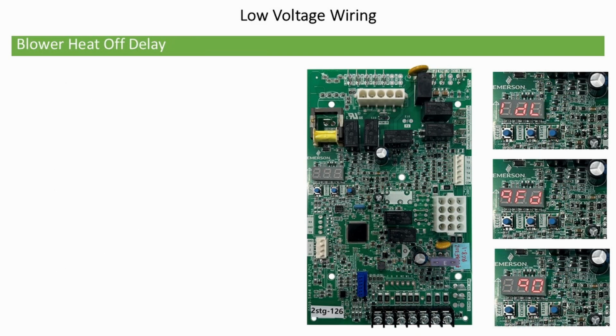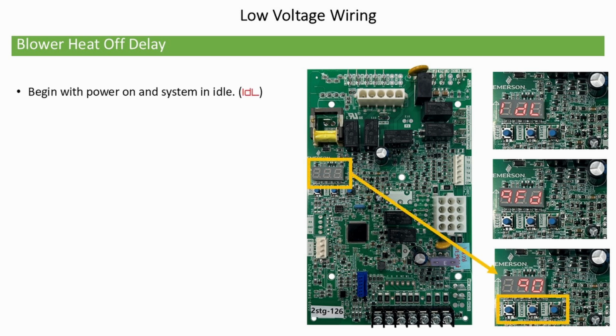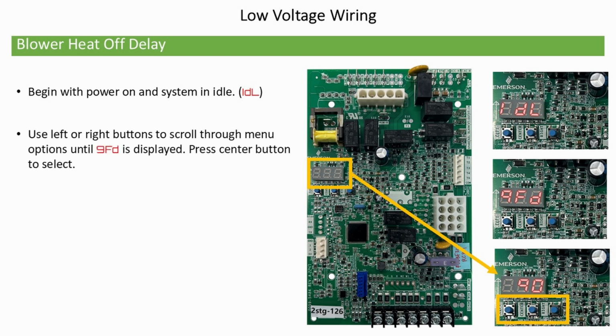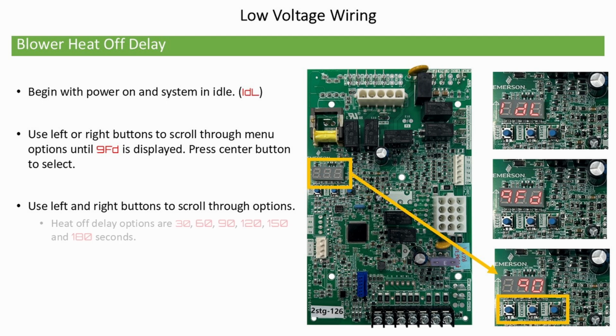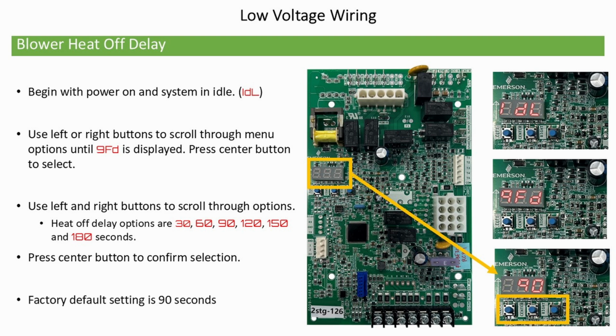Blower heat off delay. Begin with the power on and the system in idle. The display will show IDL. Use the left or right buttons to scroll through the menu options until 9FD is displayed. Press the center button to select. Use the left and right buttons to scroll through the options. Heat off delay options are 30, 60, 90, 120, 150, and 180 seconds. Press the center button to confirm the selection. Factory default is 90 seconds.